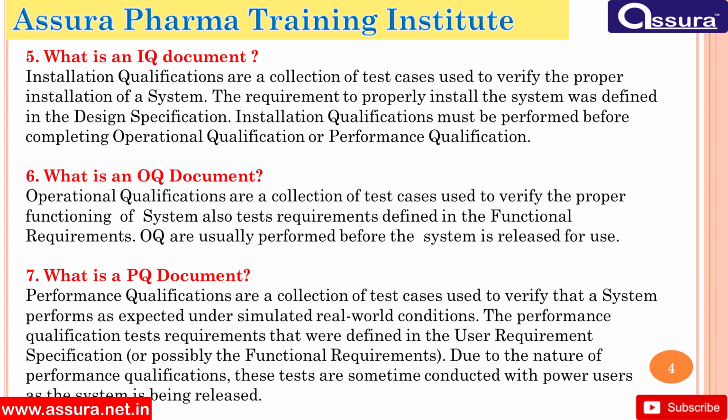What is an OQ document? Operational qualification is a collection of test cases used to verify the proper functioning of a system. Also, it tests requirements defined in the functional requirements. OQs are usually performed before the system is released for use.